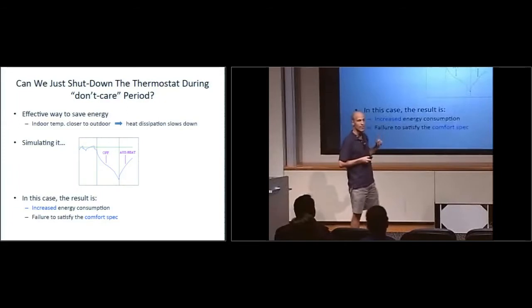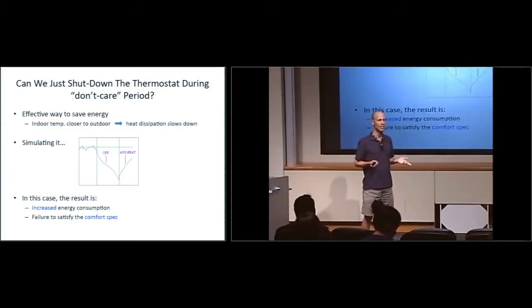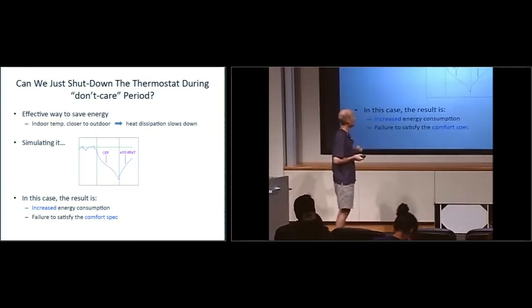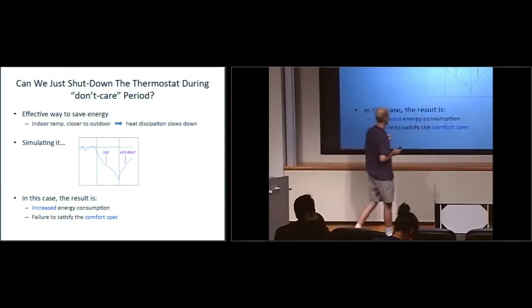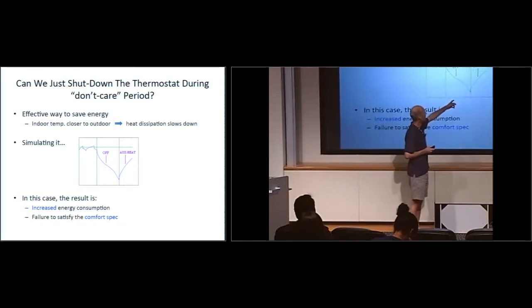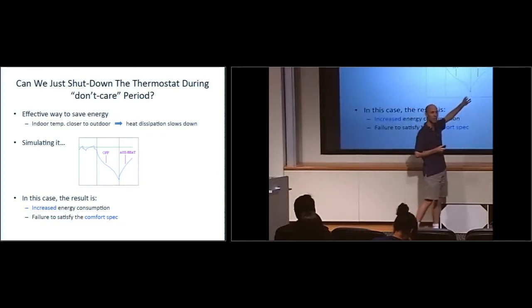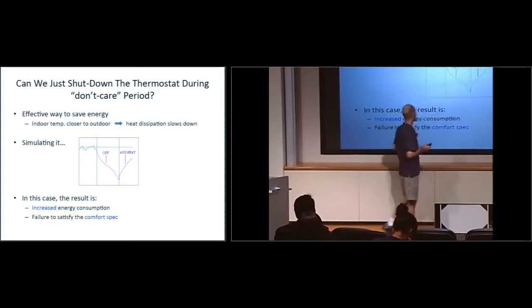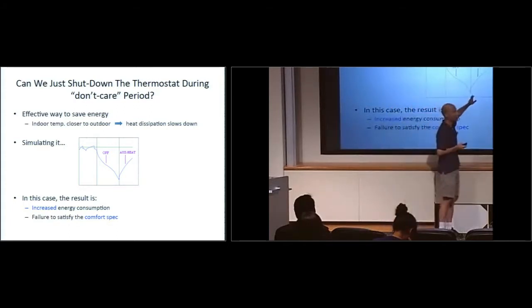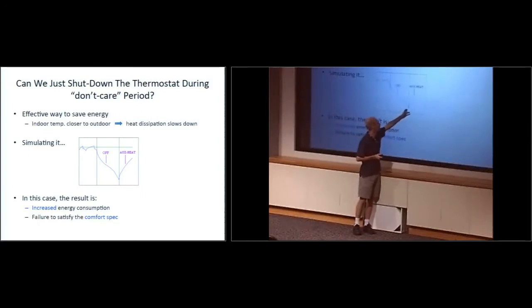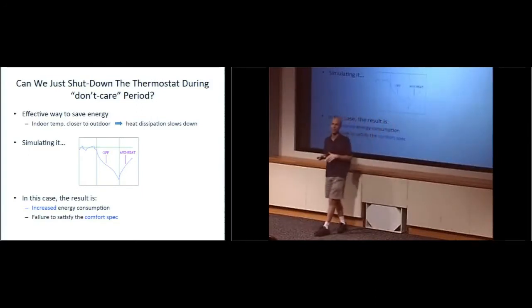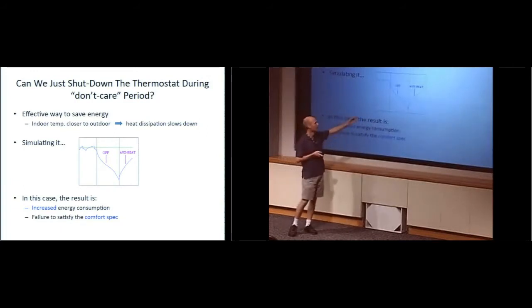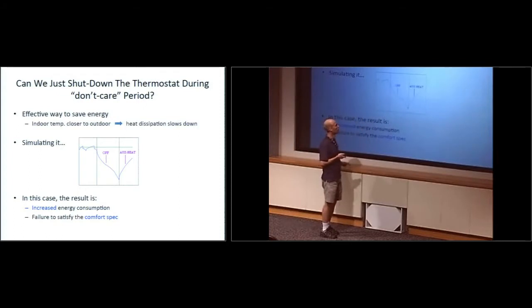A natural question: since we want to save energy, can we just shut the system down during the day and turn it on when occupants are back home? Simulating this, we actually found that this strategy consumes more energy than just leaving the system on all day. The reason is that temperature drops very low, and then the auxiliary heater kicks in and consumes a lot of energy trying to bring it back. In addition, we don't satisfy the comfort specification, since it takes several hours for the auxiliary heater to restore the temperature—here, even after 6 hours, it is still out of range.